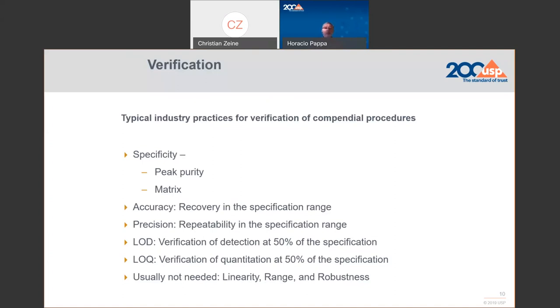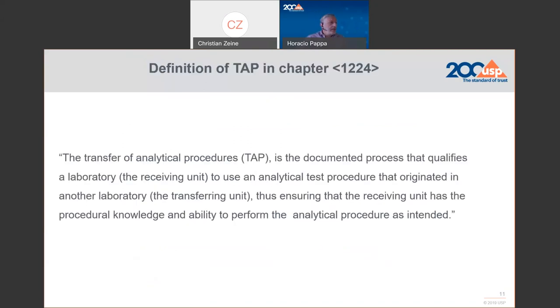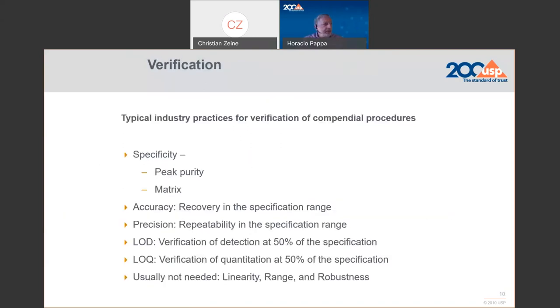You can also determine peak purity using the appropriate HPLC detector. Then we have accuracy and precision—these two, together with specificity, are the main performance characteristics that need to be tested during the verification. We have to demonstrate that the analyte is properly recovered within the range of the specification, and also that the repeatability is appropriate within the range of the specification.